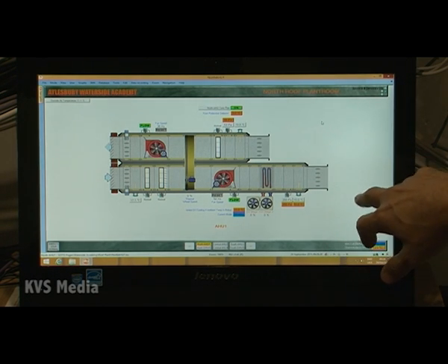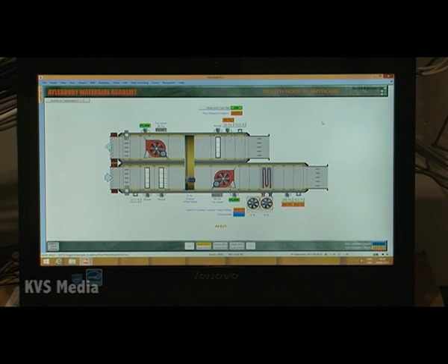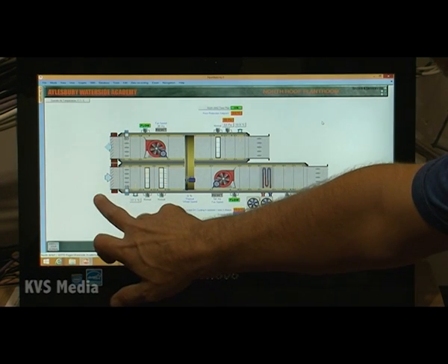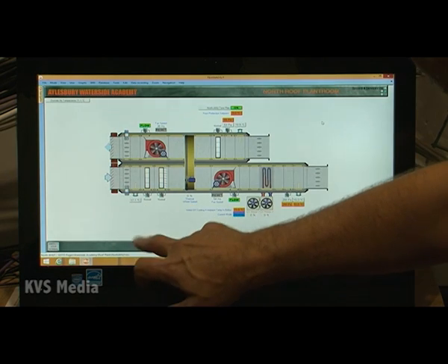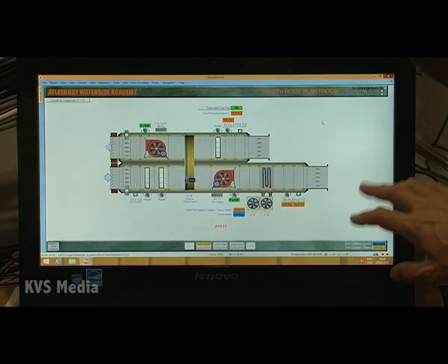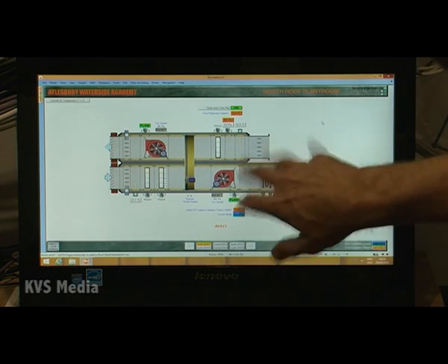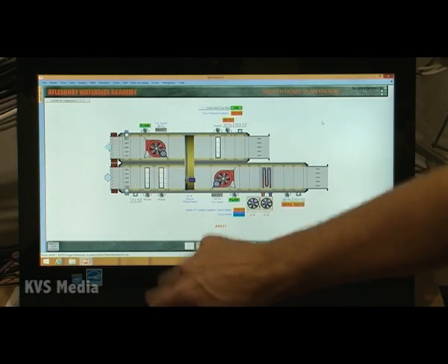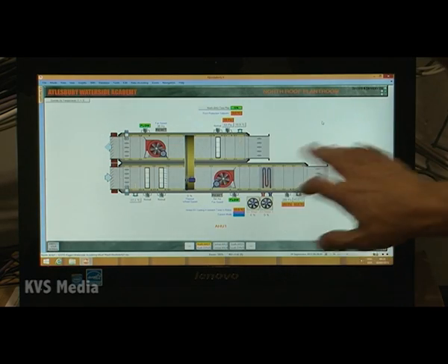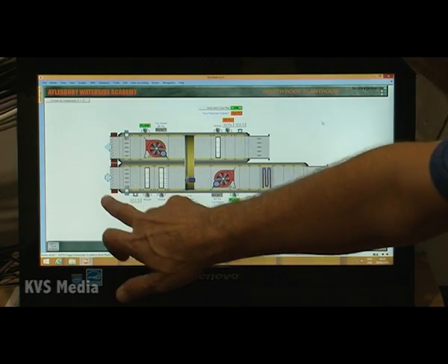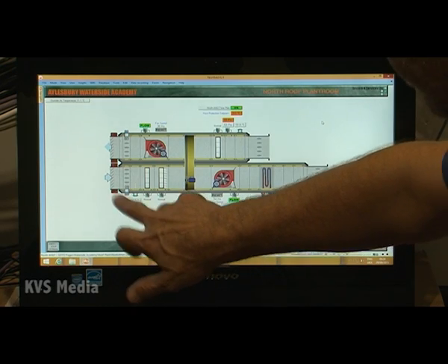So the air handling units are all fairly similar. You've got the supply air coming in through a damper. So if this air handling unit has ever been off, when it's switching back on, the first thing that has to happen is this damper has to open, and only when it is open can the fans start to run. So there's that interlock for the supply and the extract. So the air comes in, we monitor the inlet temperature.